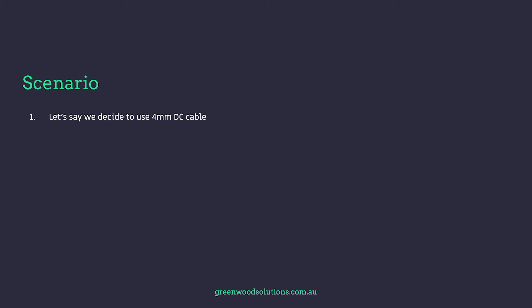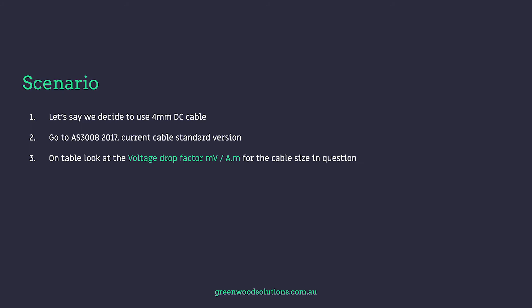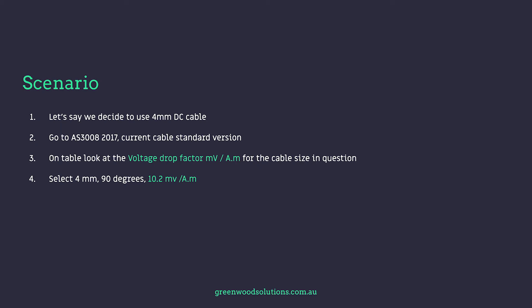Let's say we decide to use a 4mm cable. To look at the cable's characteristics we need access to AS3008 — the 2017 publication is the current one. In this method we look at the millivolt per amp metre rating for the cable in question. Opening AS3008 and looking at the appropriate table, we find that the 4mm cable has a millivolt per amp metre drop of 10.2.